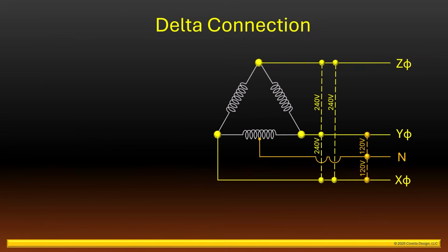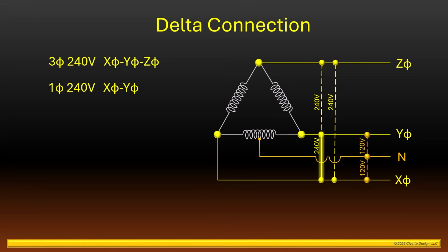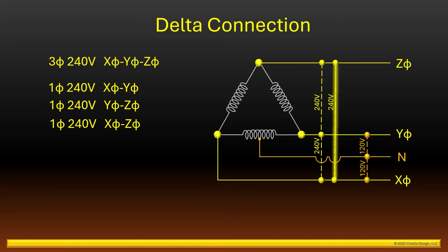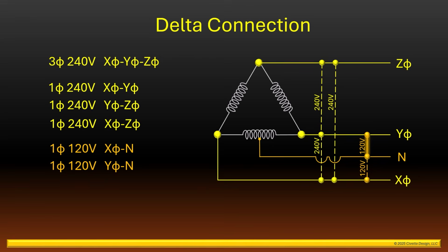Before we move on, let's take a closer look at what's happening here. This delta transformer connection is capable of providing three-phase 240 volt power by connecting all three phases X, Y, and Z. It can provide single-phase 240 volt power by connecting X and Y, Y and Z, or X and Z. It can also provide single-phase 120 volt power by connecting X phase and the neutral, or Y phase and the neutral. Take a look at what's missing here though.